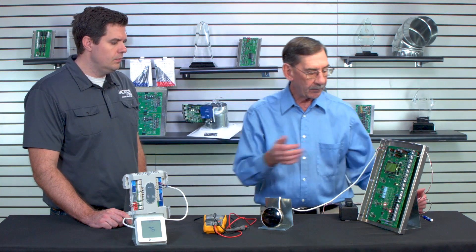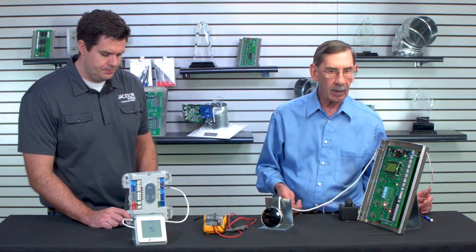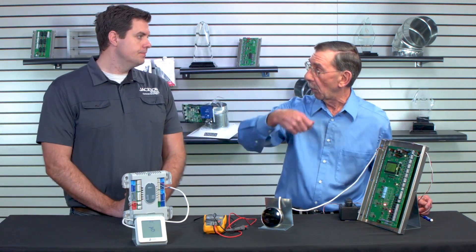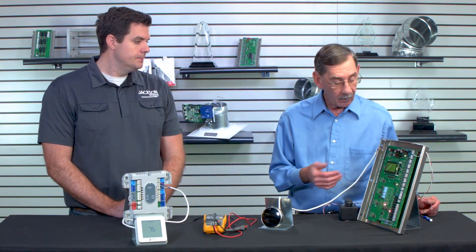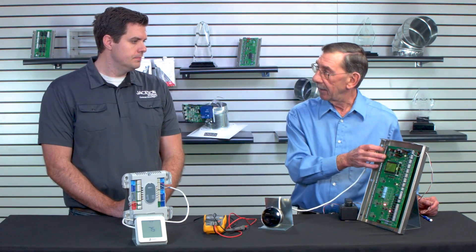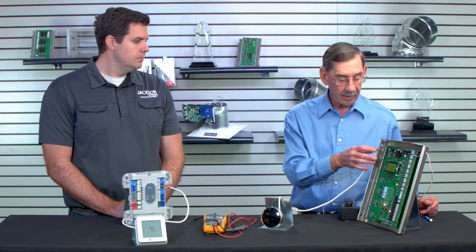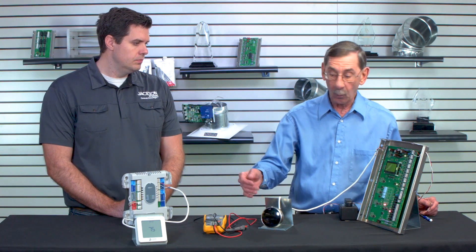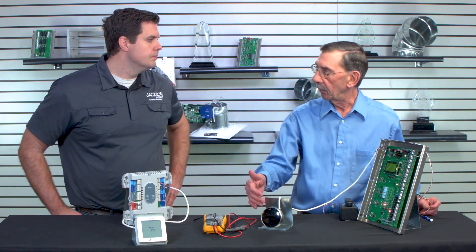A lot of times you might have a cracked wire. Even new thermostat cable can be broken. It's amazing. Or someone shot a staple in it when they were pulling the wire. It's easy to find that out because if we're not getting the input here, then it's either wire or it could be the thermostat configuration or it could even be the way it's wired to the sub base of the thermostat.